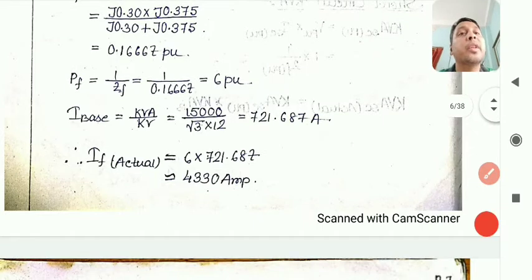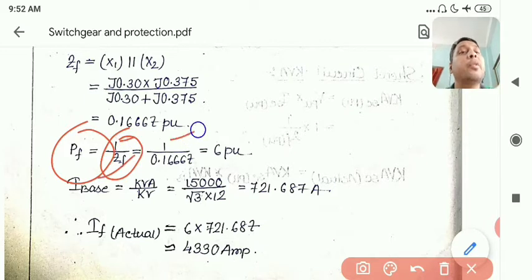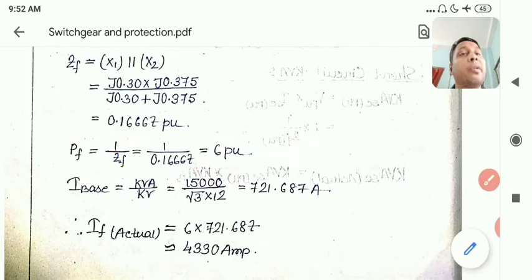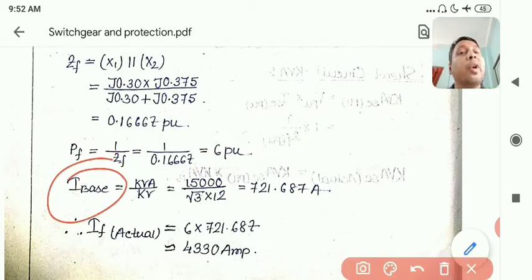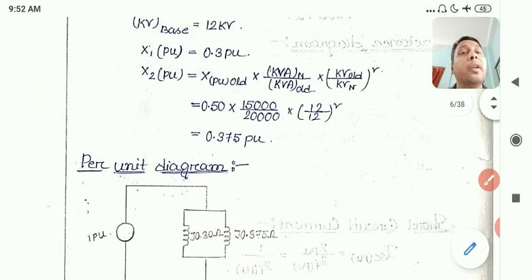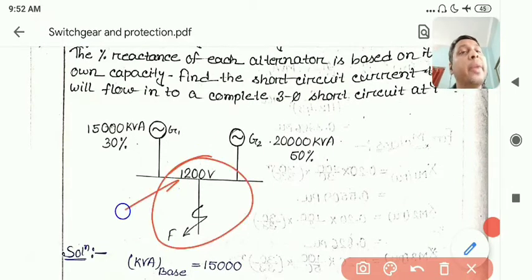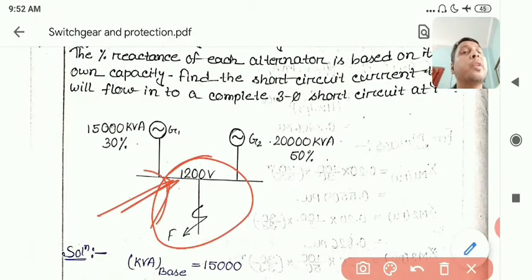The pre-fault condition is always assumed to be 1 per unit — the system was running smoothly and balanced. Now the fault current I_fault equals V_pu divided by Z_f. Since V_pu is 1, and Z_f is calculated from the parallel combination, I_fault comes out to approximately 6 pu. The base must be taken at the point where the fault is occurring.